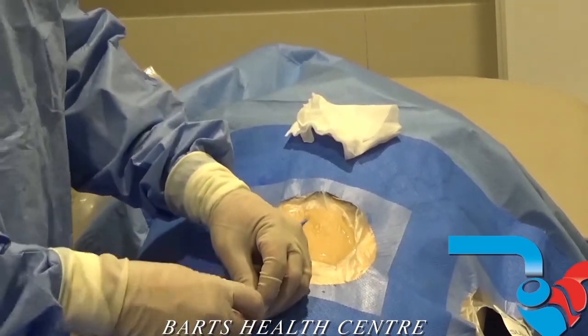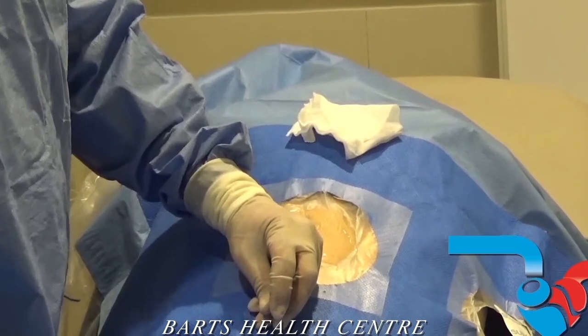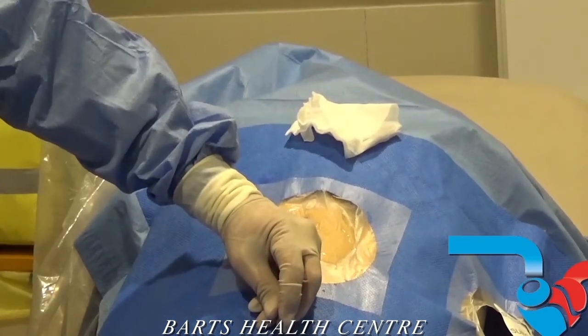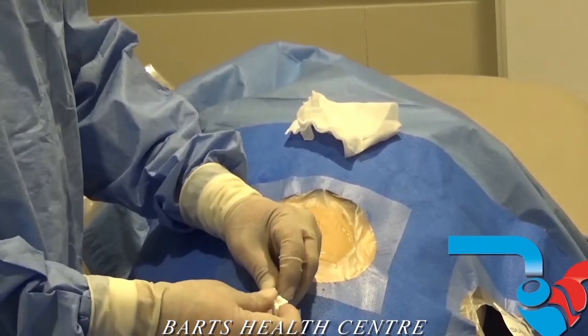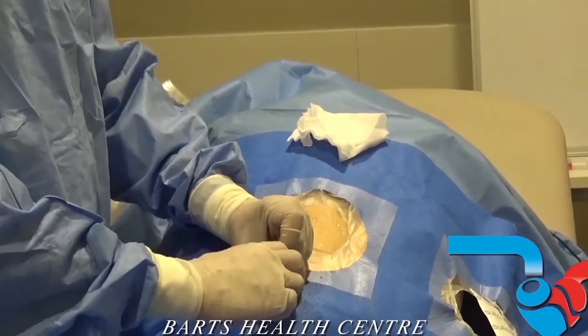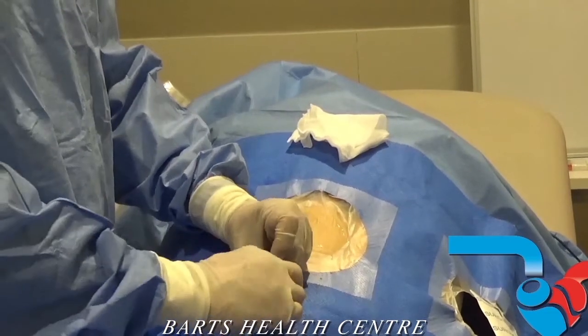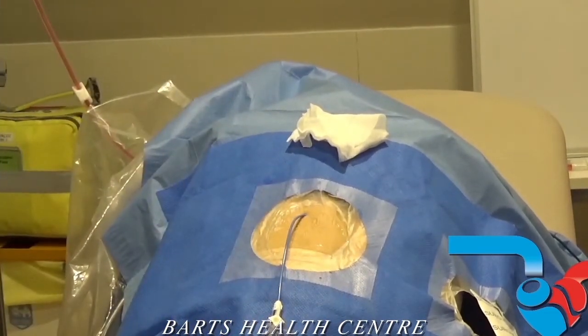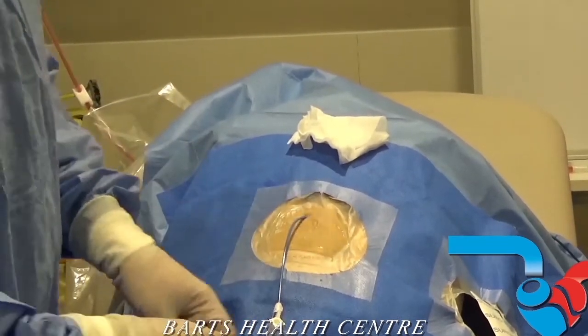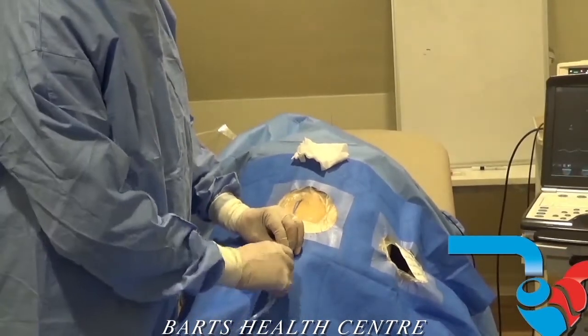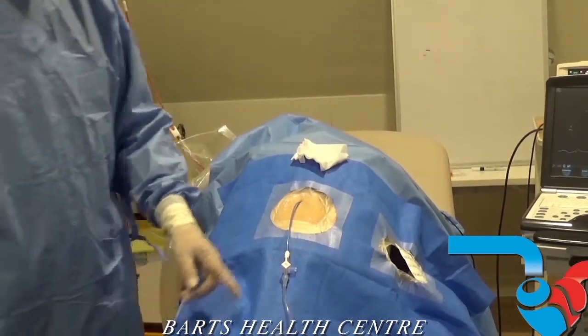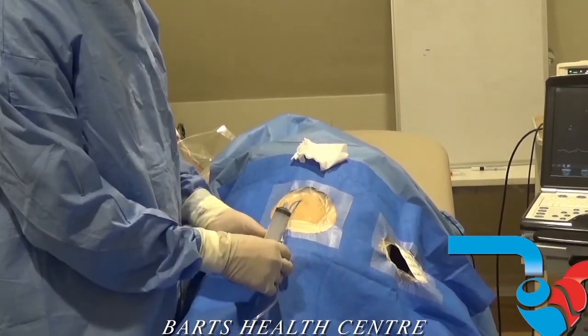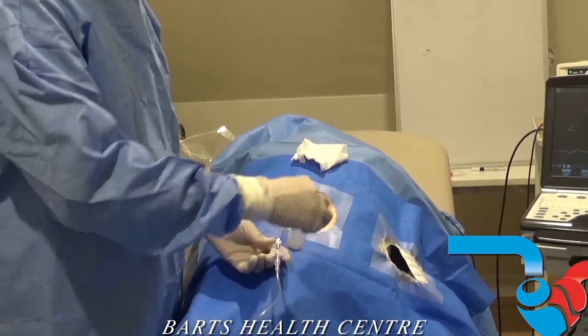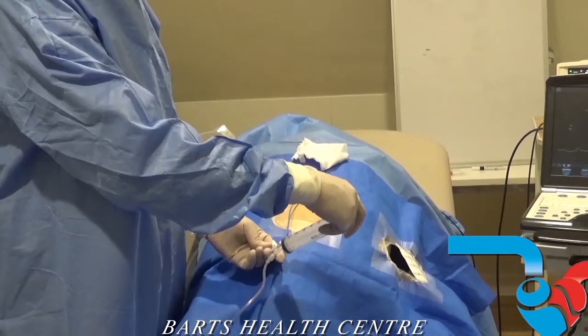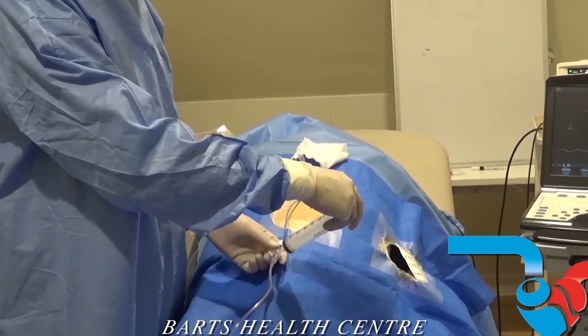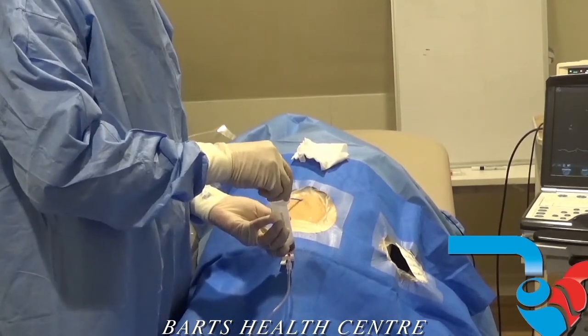I can remove the wire, and then at this point I will take one of the 3-way taps that's in the pack, and I will connect that, turn that to off. Now, it's up to you what you do at this stage. I tend to get the circuit set up so that you've connected the bag to the drain. Take your 50 mil syringe, connect that to the side port here, turn this off to the bag, and then aspirate back.